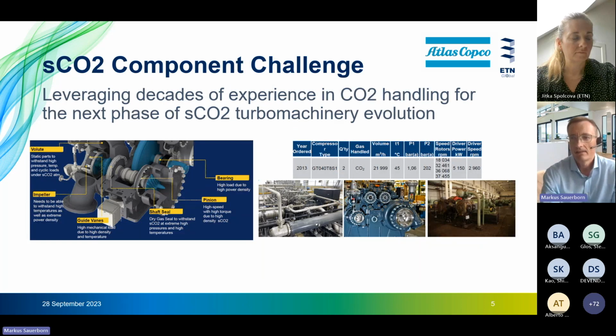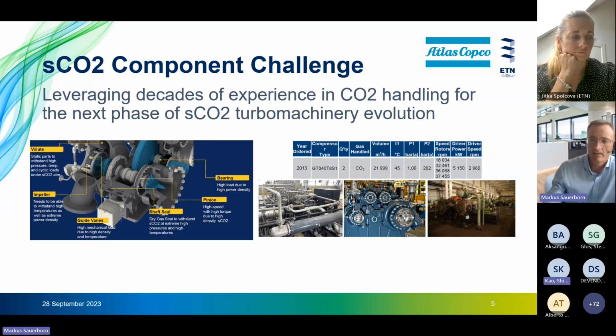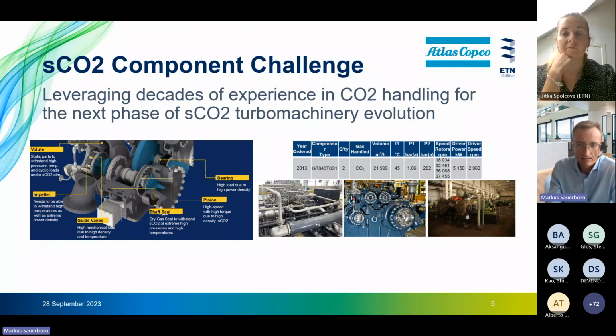Now let's come to our CO2 applications. Since we are dealing with high pressure, temperature, and power density, the mechanical design of the machine is a challenge. The picture on the left side is taken from a high pressure CO2 compressor, but is valid for an sCO2 expander as well. At a glance, you can find the critical components like volute, impeller, guide vanes, shaft sealing, bearings, and gear set, which need to withstand extreme conditions in sCO2 applications.